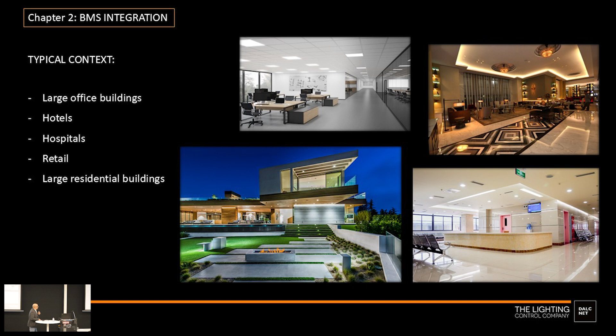So for this reason, it is important to understand that sometimes DALI is just a way to transmit a signal, and the control system is something else. So the supervisor is not a DALI application controller sometimes, but is another system, another software, another platform. Okay, and so we start to see the different types of this BMS integration. I start with probably the most simple one, one of the most diffused, and one of the most critical also, which is the KNX to DALI integration.